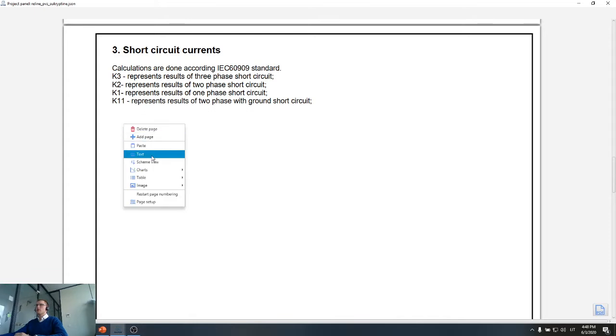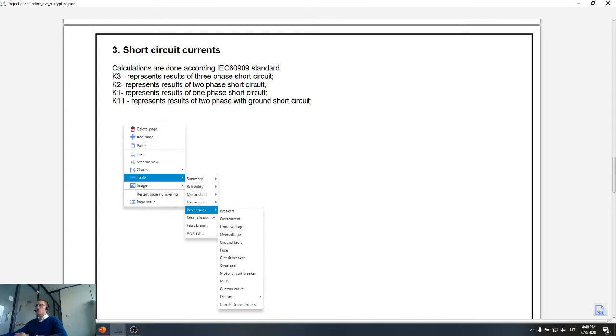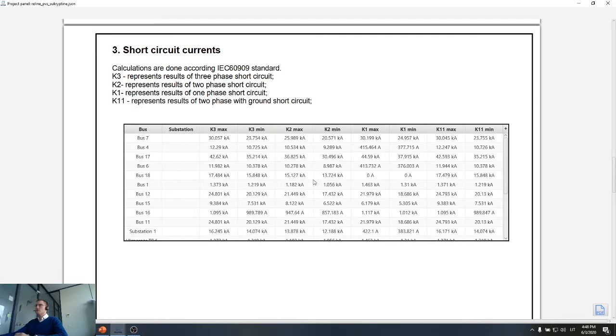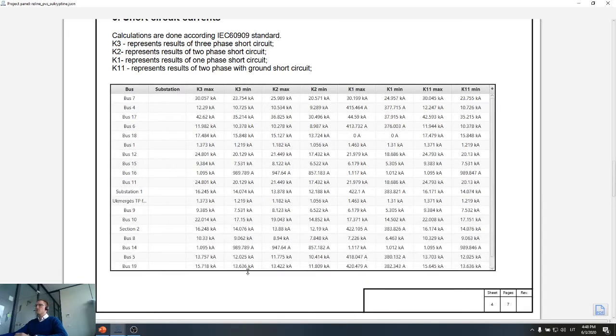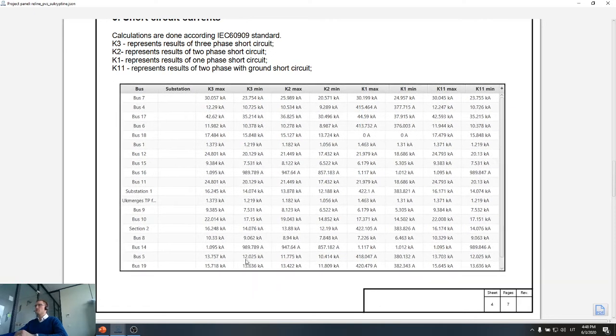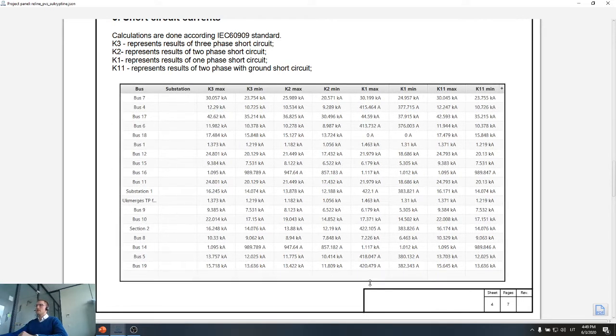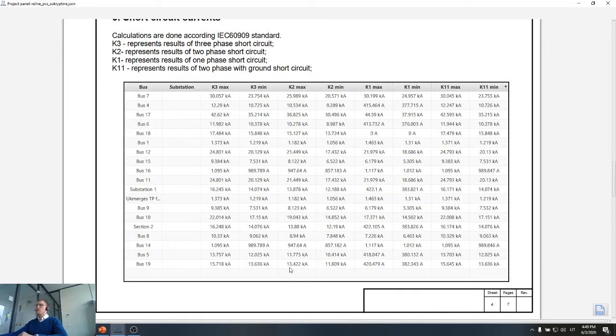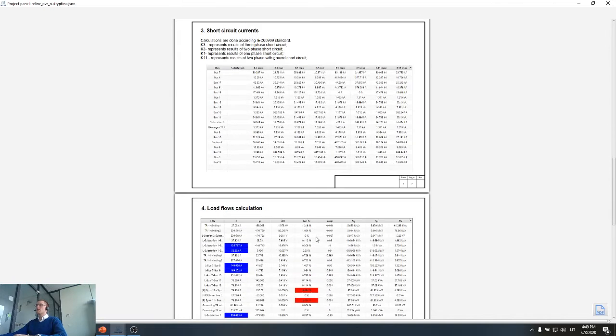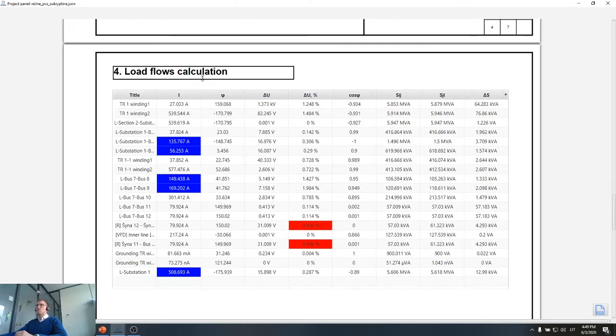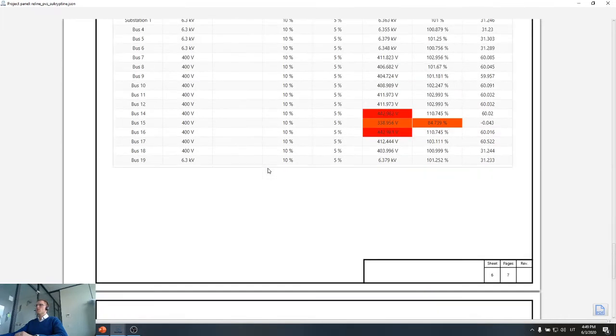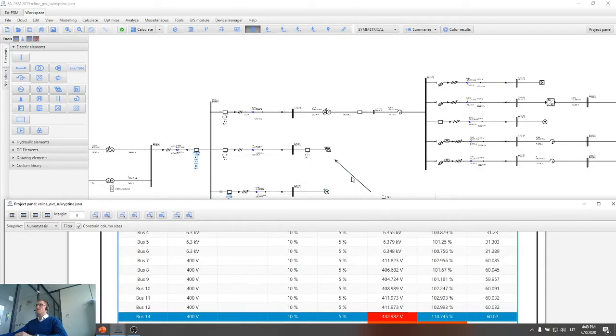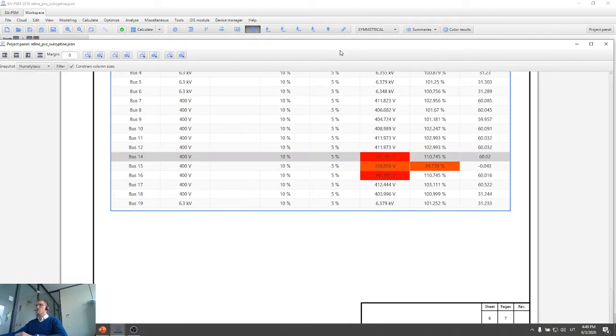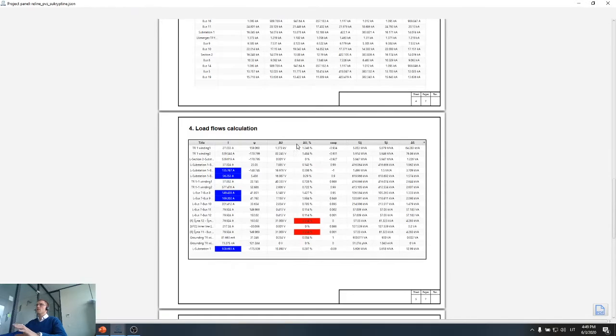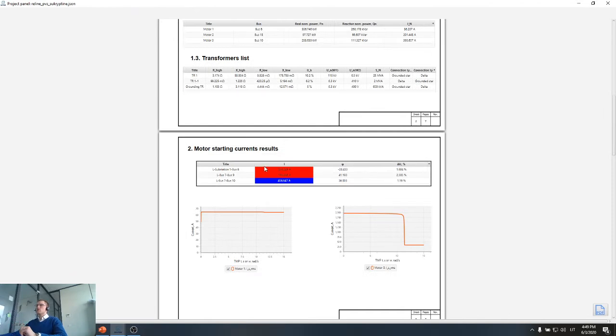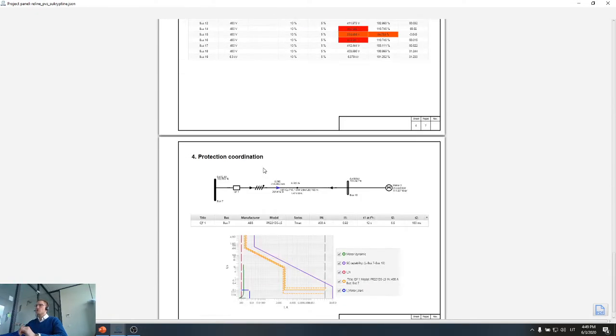Let's delete it from here and add one more time. So I go to table, I go to short circuit all branch results, and here we have the table already added. So in order to add this to your report, you have to export to Excel. You have to then add it into a Word document, while here in EA-PSM you can automatically add the table directly into PDF. Here I also have information about load flow results. So load flow results should also be added to the table. So basically these are the three most important result types: load flow, short circuit, and motor starting results that you need to provide in the protection coordination report.